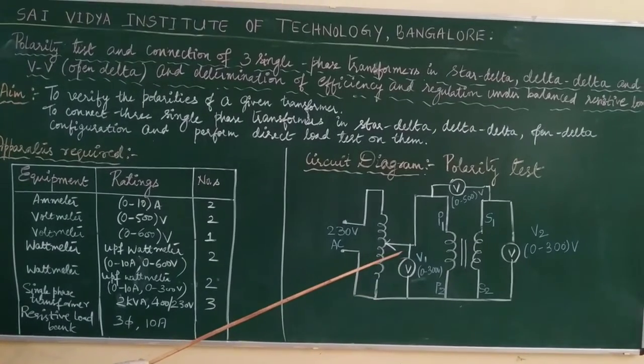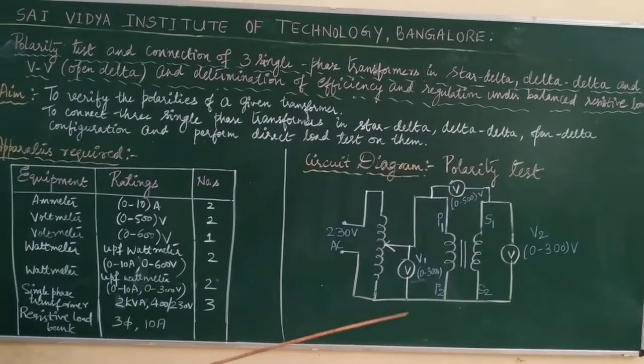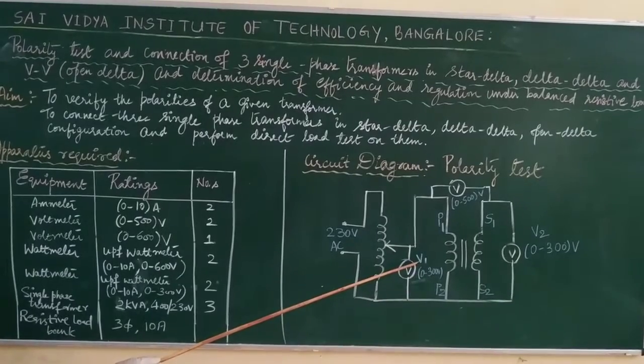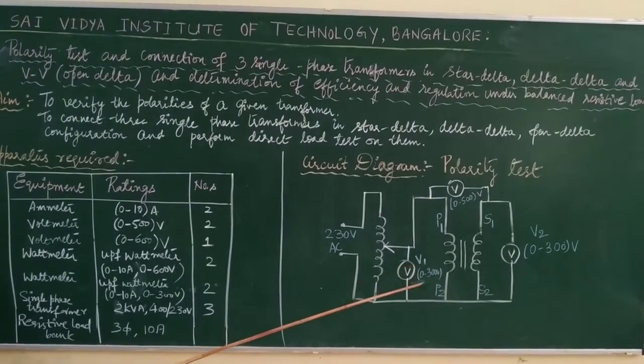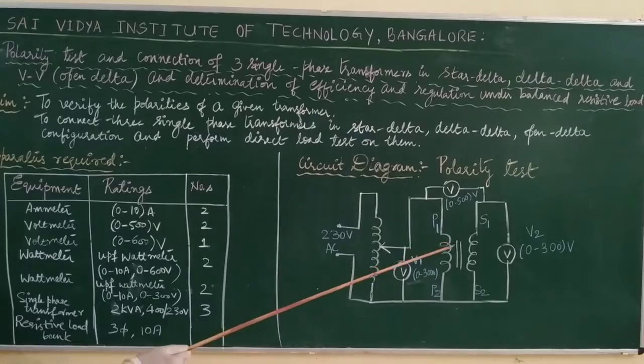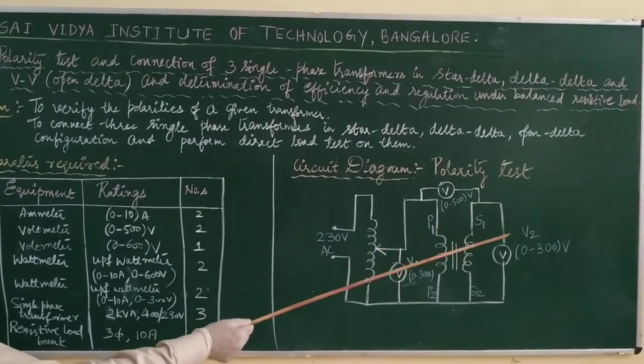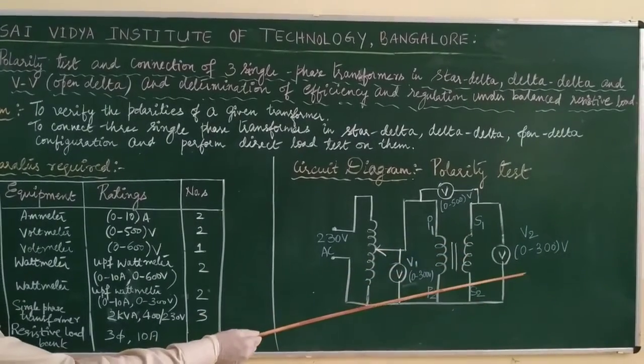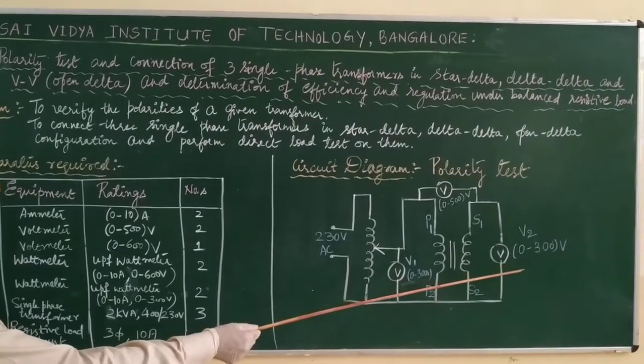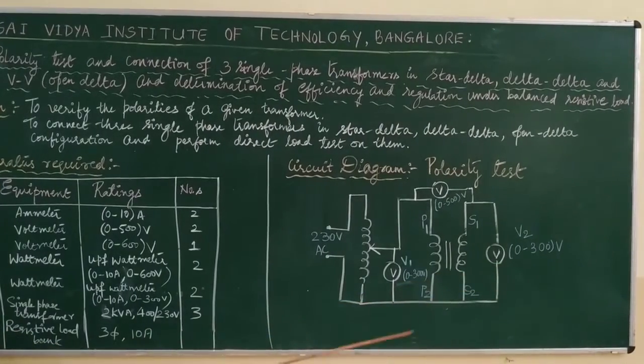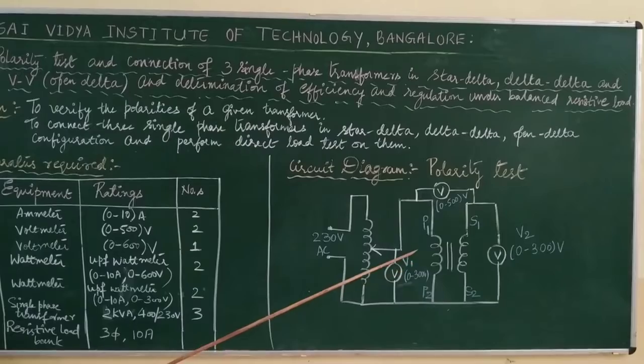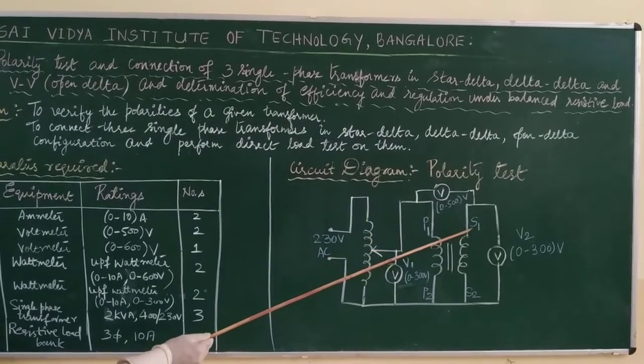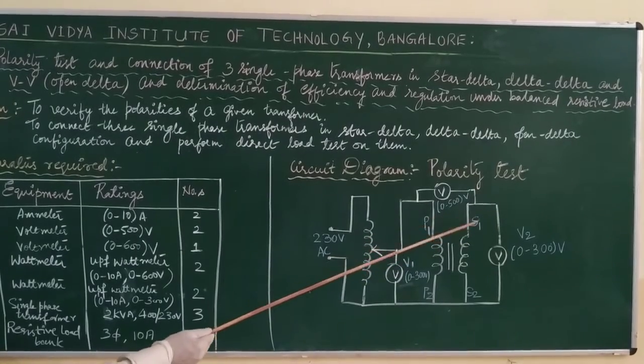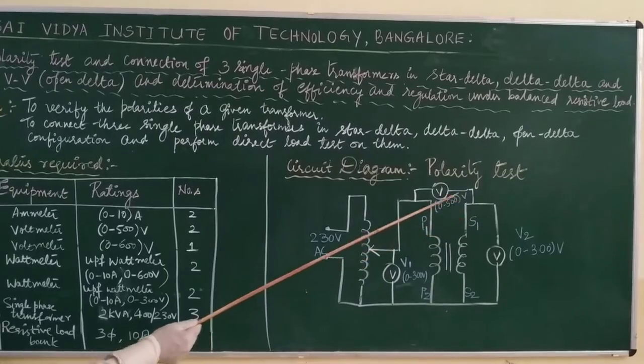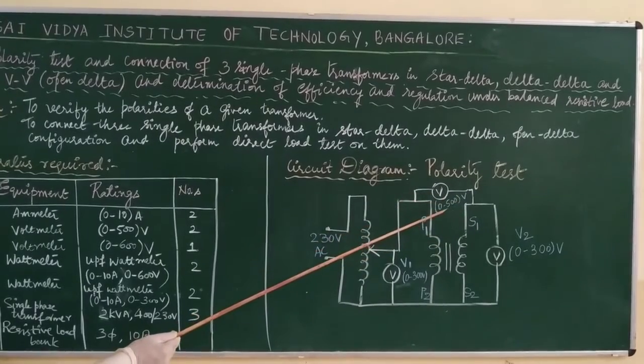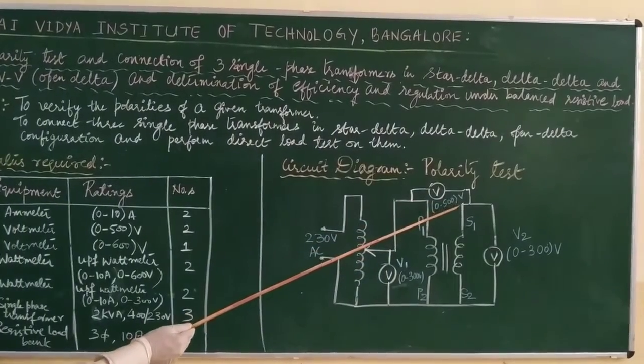Then we have a voltmeter in order to measure the primary voltage, and the notation for this is V1. Its range is 0 to 300 volts, and along the secondary we have another voltmeter connected across the secondary, and that voltmeter range is 0 to 300 volts. Now we have a voltmeter connected between P1 and S1, primary of the transformer and secondary of the transformer, and its range is 0 to 500 volts.